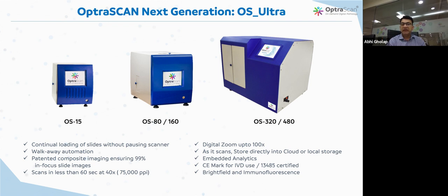And then this scans at 40x or equivalent of 40x in less than 60 seconds. So it can produce an image in an optical configuration of microscope at around 40x with 75,000 pixels per inch. And this same image can be digitally zoomed up to 100x as well. As it scans, it has an option to store locally, or you can configure it to store it into the cloud. So this system can even sit on your administrative desk, where along with the documents, your administrative assistant can also scan the glass slides and then push it into the cloud or the local storage.